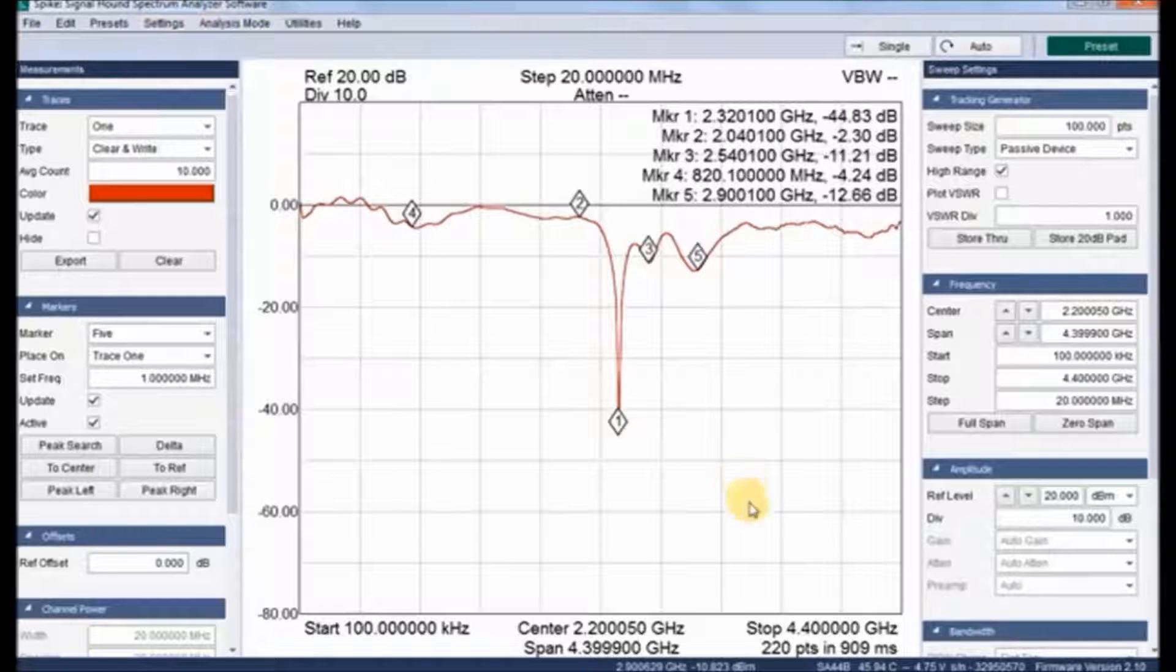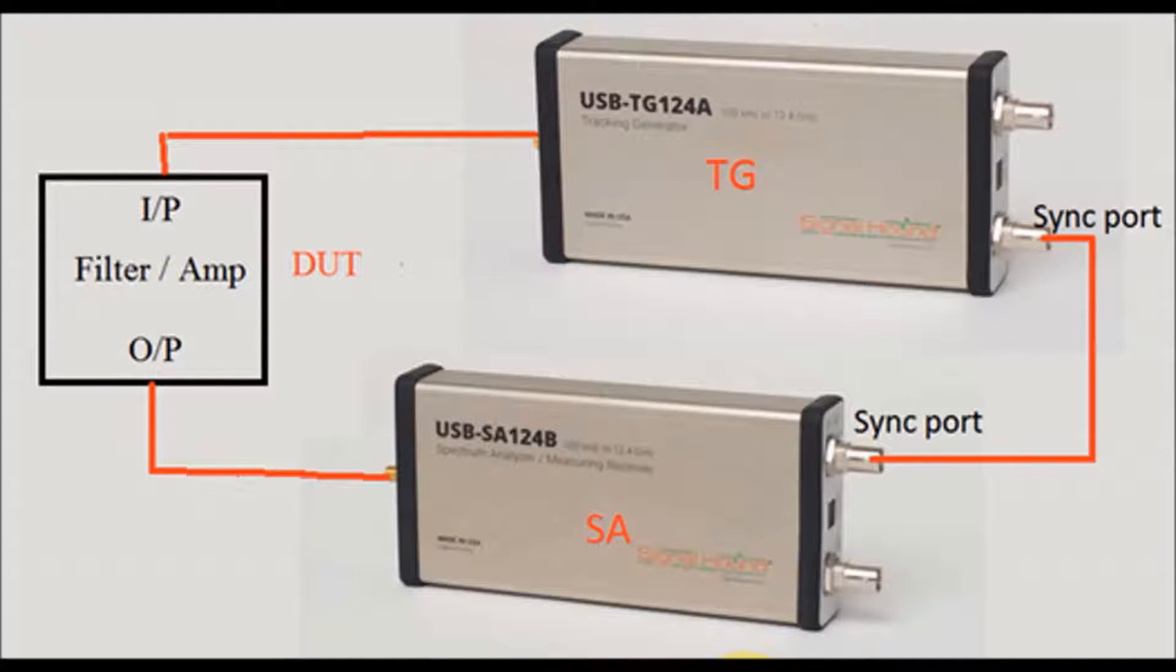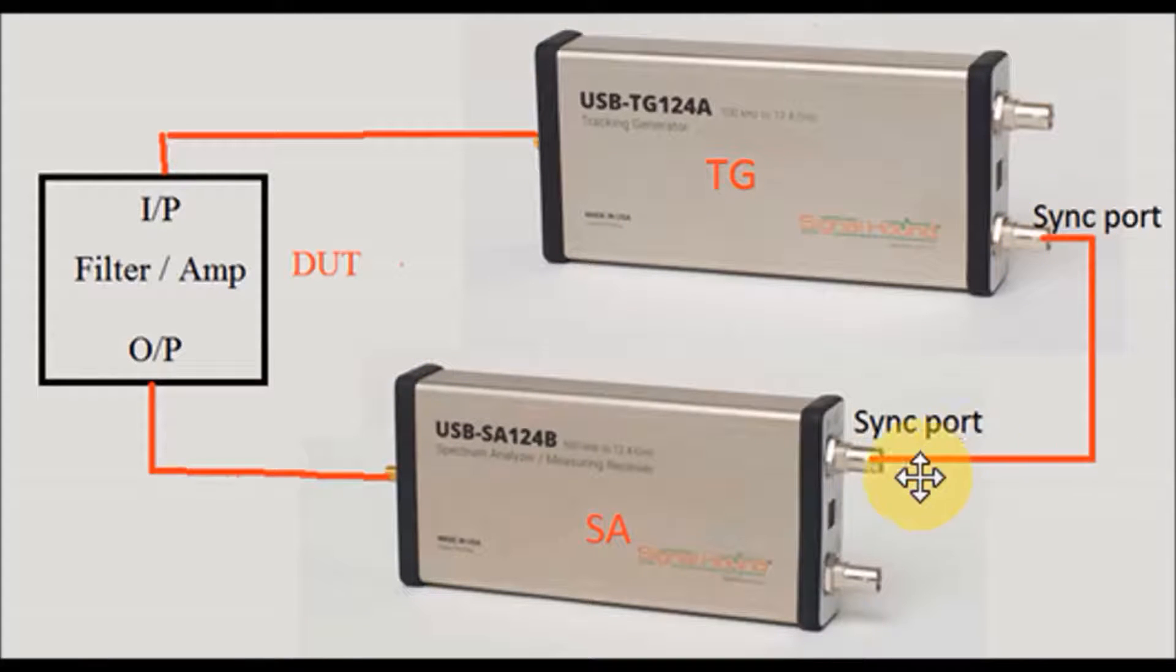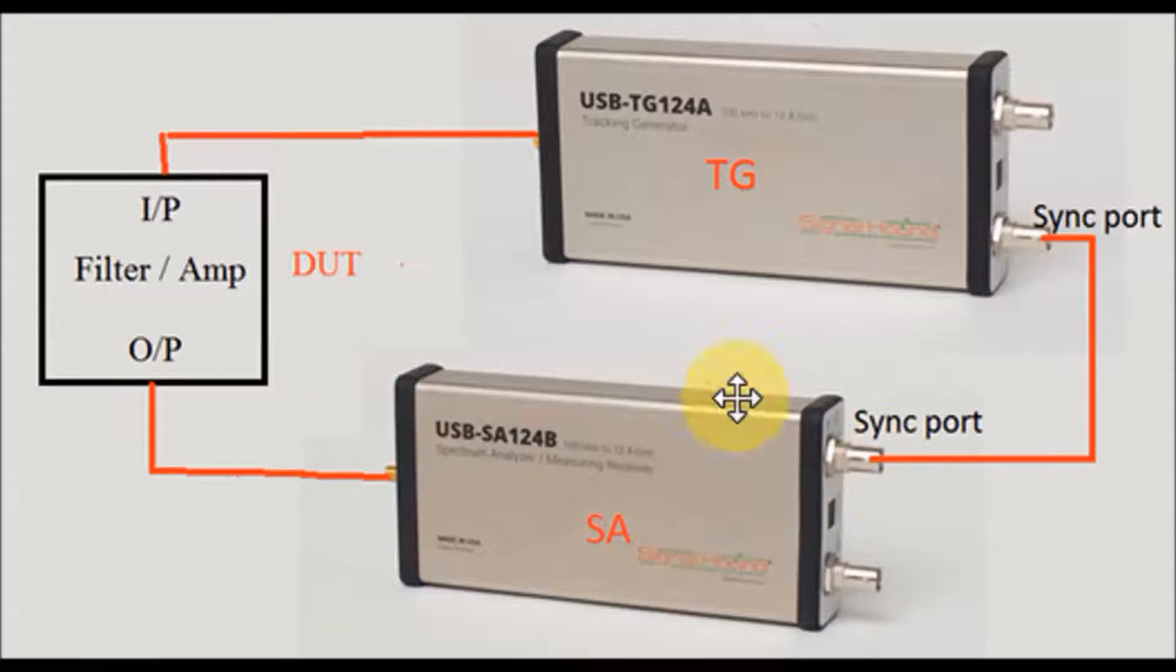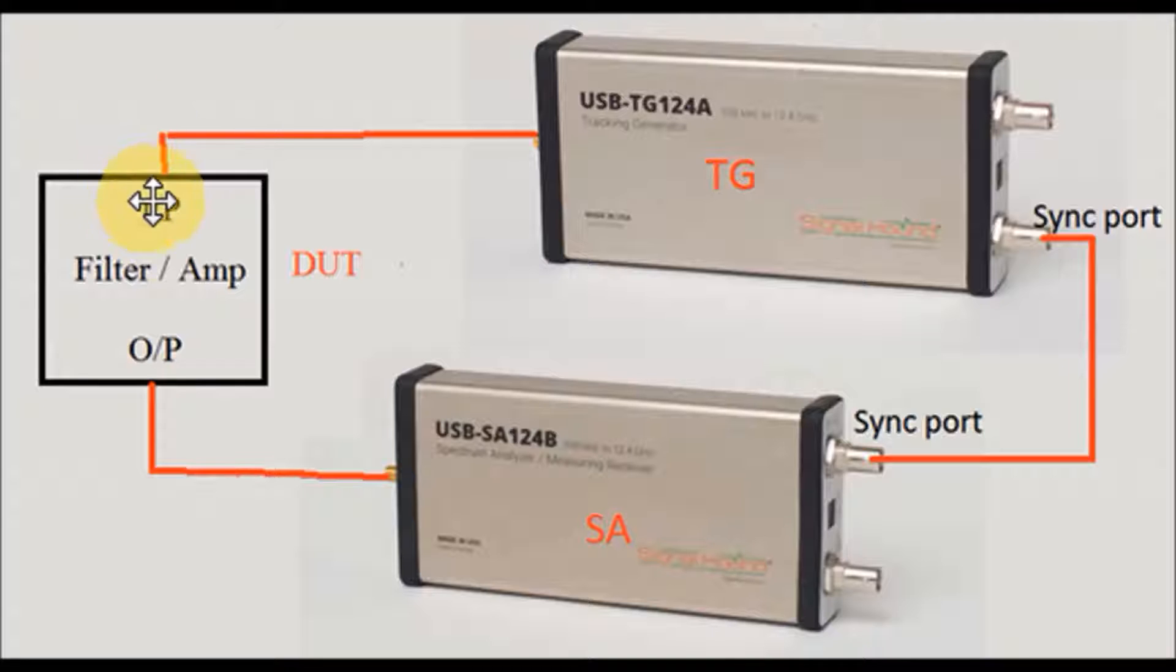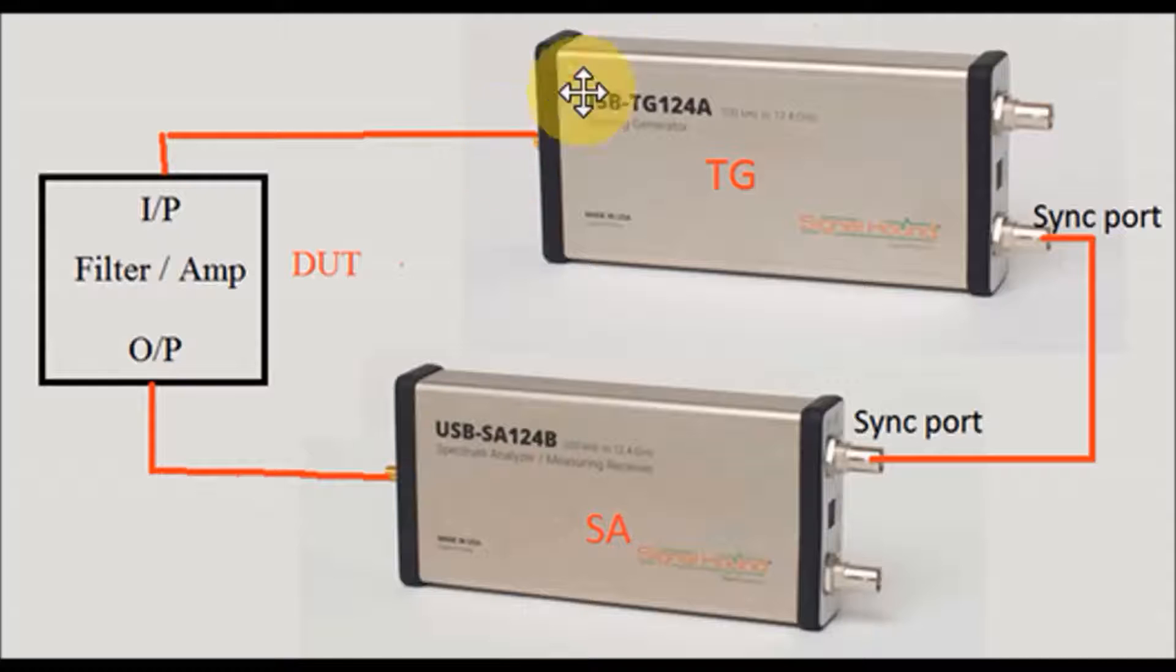This is the connection setup for S1,2 and S2,1 parameters. These parameters are useful to measure insertion loss, gain, isolation, reverse isolation, etc. The two synchronization ports at the N-type panel are connected together, and from the DUT input port is given to tracking generator, and output is given to spectrum analyzer.